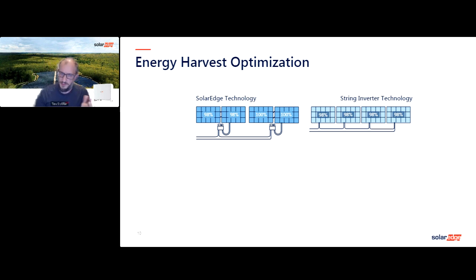Higher power modules, you don't want that many in the string, just because you're limited on the output current. But you could have up to 30 optimizers, 60 modules in a string, which provides basically twice as long of a string, which means less home run connections, less everything else, less number 10 wire. And you can very easily see the effects that brings.